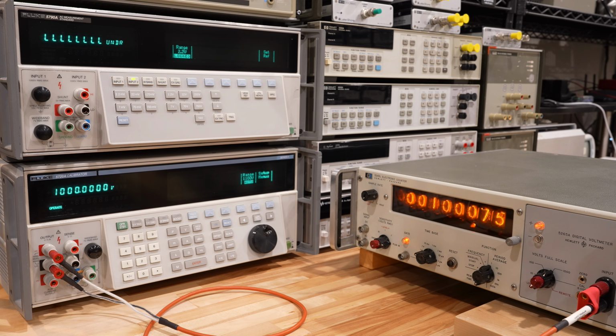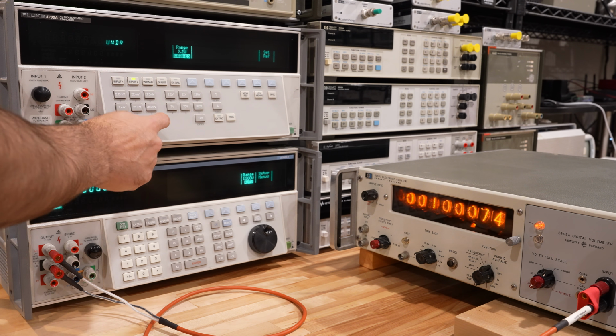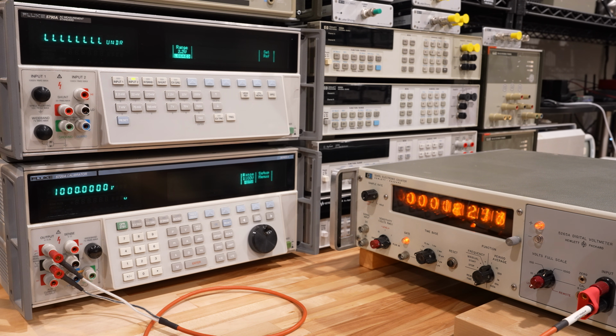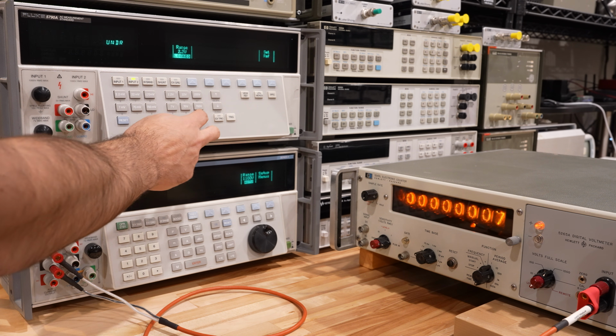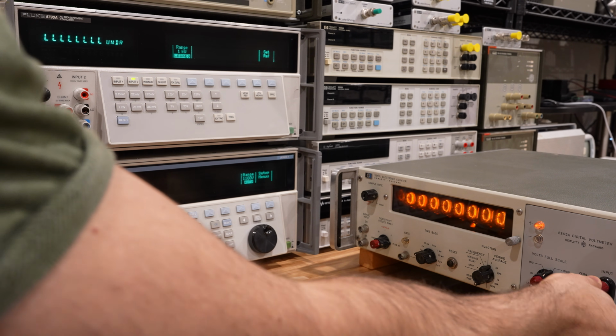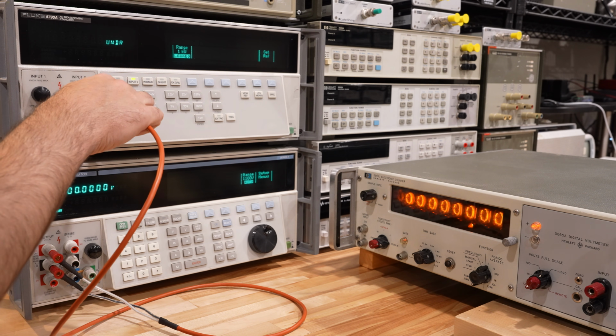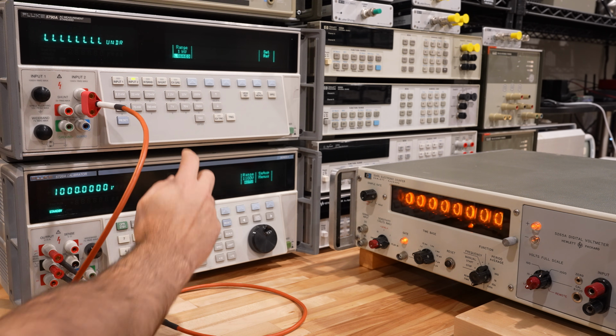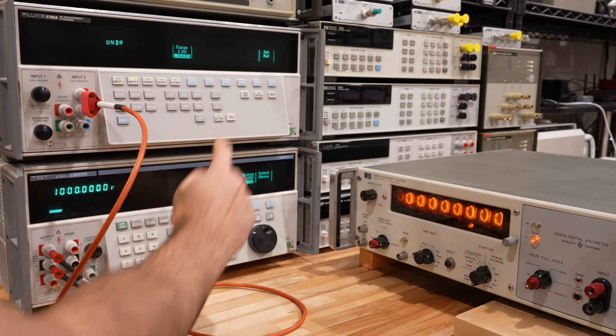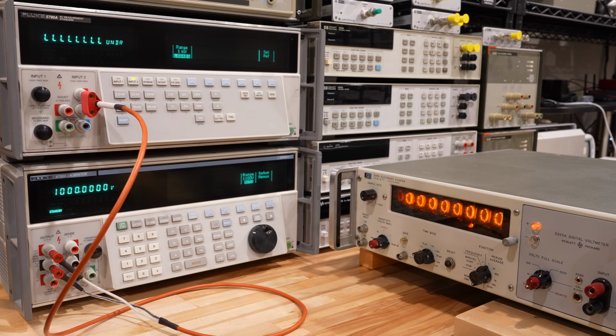Look at that, 1000 volts. So it's reading 0.7 volt off, which is again quite a bit. We can also validate that onto this instrument as well to make sure that it is indeed correct. Let's put this into the 1 kilovolt range. Take that from here. Plug it over here, double check, make sure this is in 1 kilovolt range. That is good, 1000 volt. And enable that. Let's see what we did at the top over there.